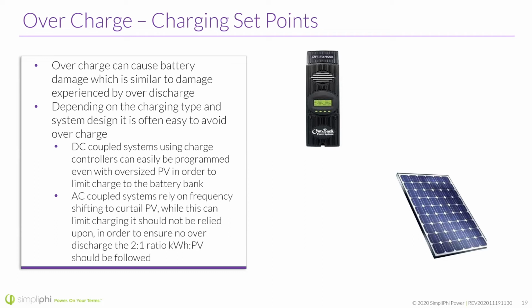AC coupled systems are a little bit different. They rely on frequency shifting typically to curtail PV. While this can limit the charging, we don't recommend you rely upon it. I've seen too many times in the field where the system does not curtail fast enough. Let's say you've got 10 kilowatts of PV and you're trying to curtail it down to 8 to charge the batteries. And it's just not quick enough, and it overcharges the batteries and it can hurt the batteries. It dumps that entire array into it. So we just recommend sticking with that 2-to-1 ratio. So if your battery bank is 16 kilowatt hours, don't go higher than 8 kilowatts of PV. That way you never run the risk of overcharging when it comes to AC coupling.